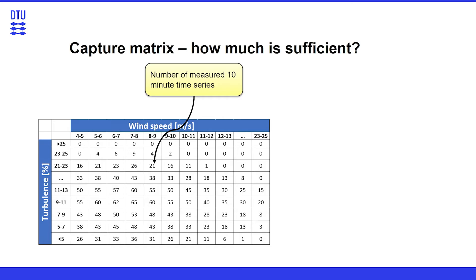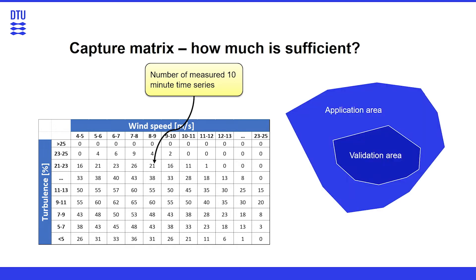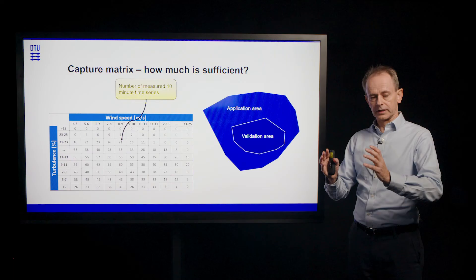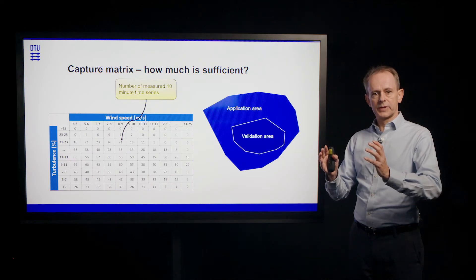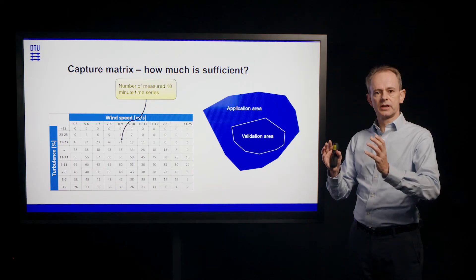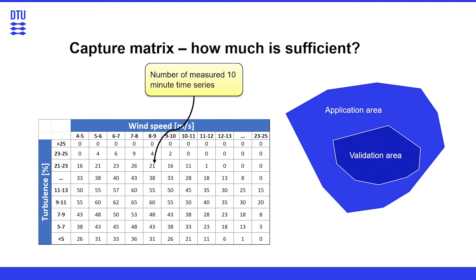The minimum requirements for that are described in the IEC 61400-13 standard. And what we need to ensure now is that the application area is covered as much as possible from the validation area. Meaning, we need to ensure that we have measured as much as possible of the wind speeds in which the turbine will operate during its life cycle.